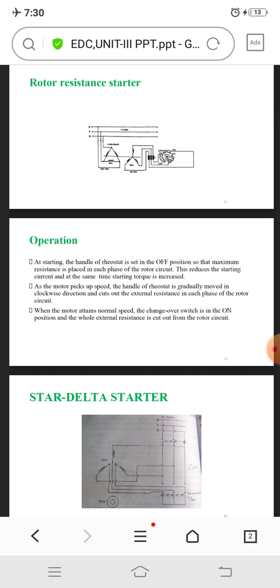When the motor runs under normal condition, the rings are short circuited and the brushes are automatically lifted from them. Slip ring motors are invariably started by rotor resistance starting. In this method, a variable star connected rheostat is connected in the rotor circuit through slip rings and full voltage is applied to the stator winding. At starting, the handle of the rheostat is set in the off position so that maximum resistance is placed in each phase of the rotor circuit.